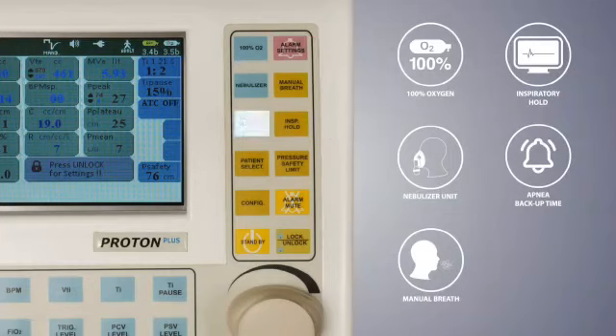Apnea backup time: There are two modes which have apnea backup facility - PSV auto in which PSV is the primary mode and CMV PC as backup, and VS auto in which VS is primary and PRVC as backup. In case of apnea condition, apnea backup mode is activated, and as soon as the patient starts efforts to breathe, it gets back to its original mode.